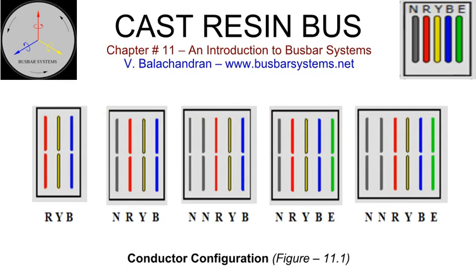For ease of fabrication and assembly, the spacing is kept in a manner so that a straight conductor, coming out of casting, will align with the fish plates of the site joint assembly. For the low-voltage cast resin bus, the phase spacing will be more than one conductor thickness to accommodate the fish plate and insulating barrier plate at the site joint. A low-voltage cast resin bus can have several conductor configurations depending upon the system parameters. It is advisable to have an embedded protective earth conductor running along with the phase and neutral conductors. This will provide a low impedance path for the earth fault current.